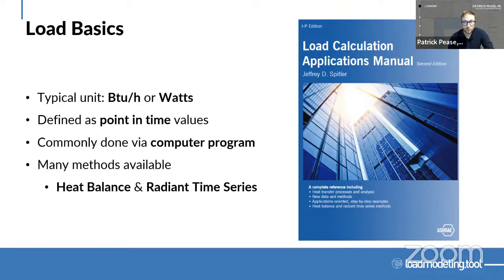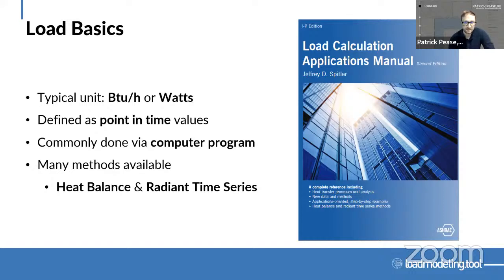These calculations are typically done with a computer program. There are means to do it by hand — we had to calculate loads far before computers — but I certainly wouldn't recommend that today; they are time-consuming and very difficult to do at scale. There are many methods available: heat balance and radiant time series are by far the top two. You can see these in many calculation programs, and even in ASHRAE Fundamentals they discuss the various differences. But they all essentially get you to a similar answer: how much heat is in my space and what do I need to deliver to counteract it?